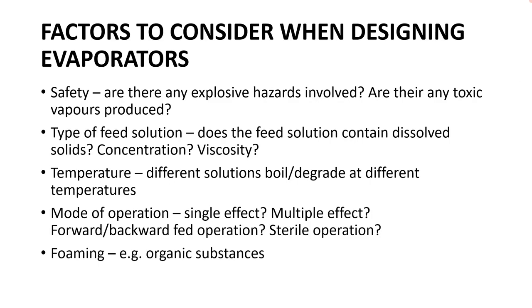The temperature of the evaporator is also another very important factor, because different solutions boil at different temperatures. Moreover, some solutions are more sensitive to temperature than others and therefore may degrade at even low temperatures in the evaporator. For these types of solutions, vacuum operation is useful as the reduced pressures result in a lower boiling point.